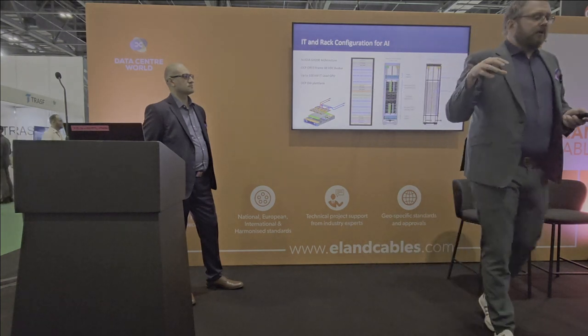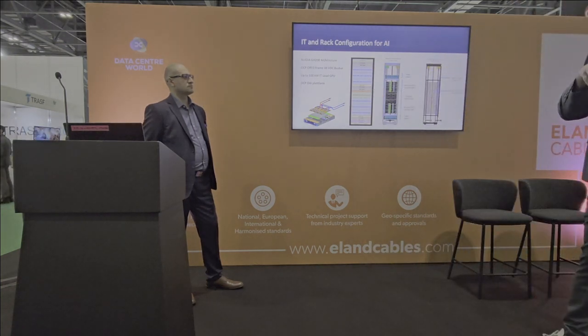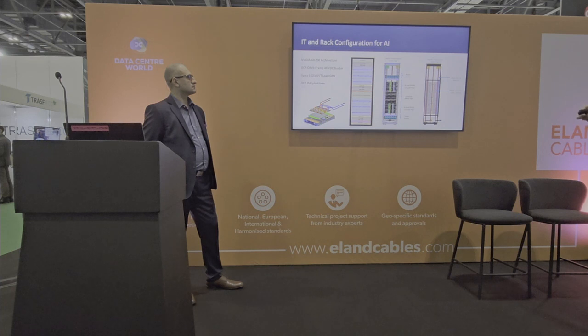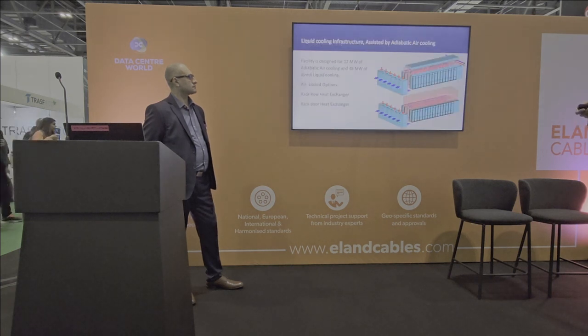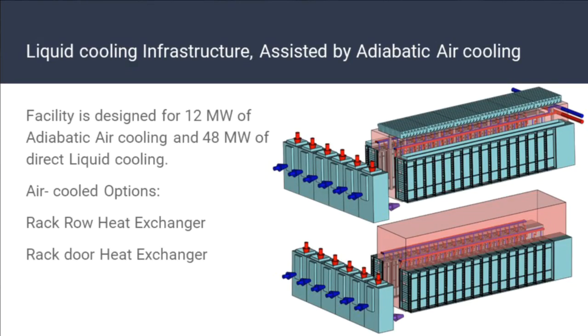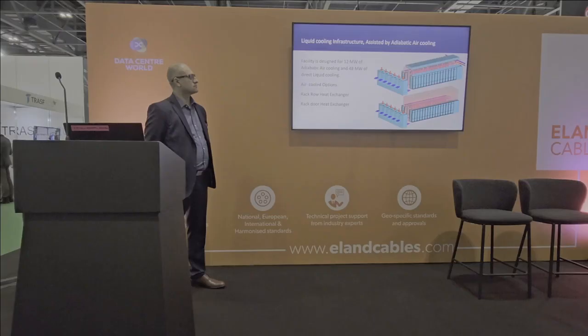So the majority of heat is rejected through direct liquid cooling. We then put those in a double rack row concept in pods that either can be direct free cooled, or assisted with heat exchangers, either row-based or on the rack door front. So those are the options.